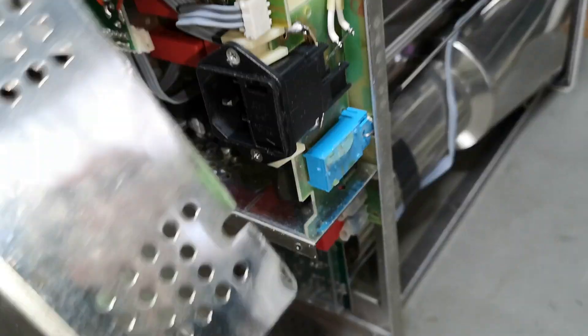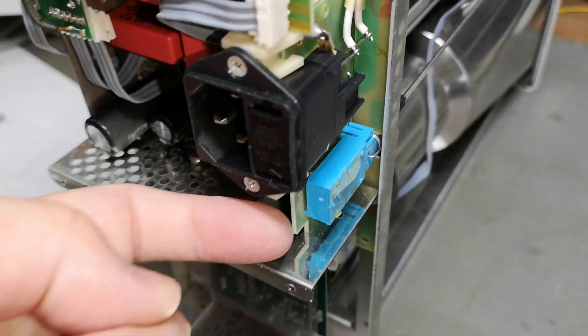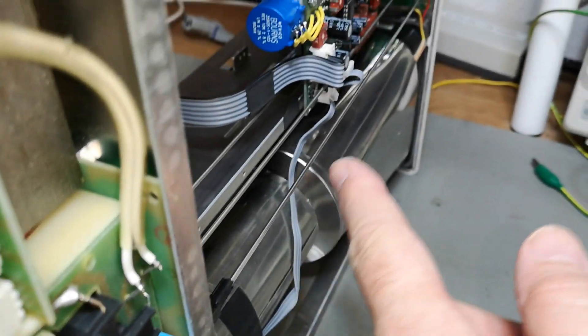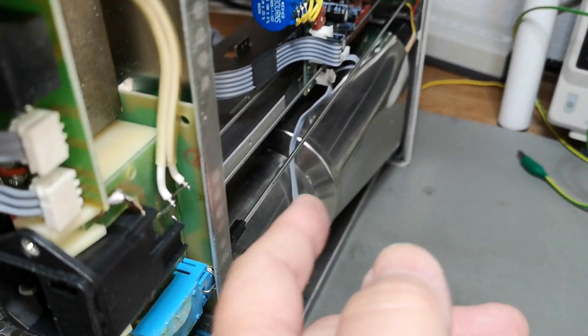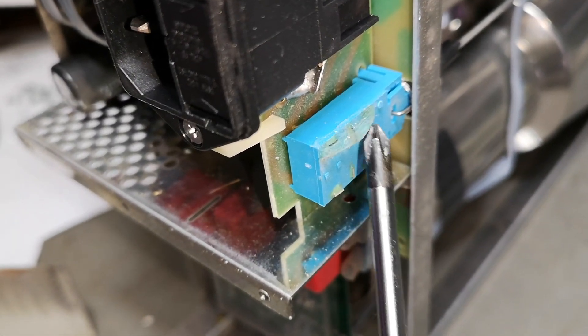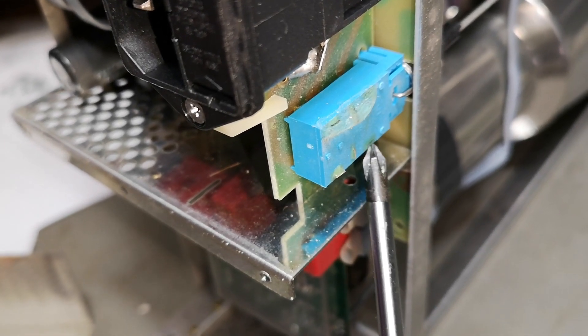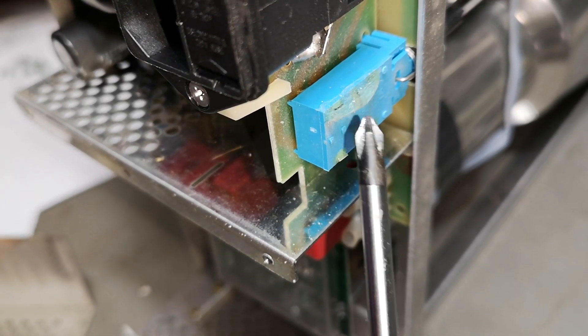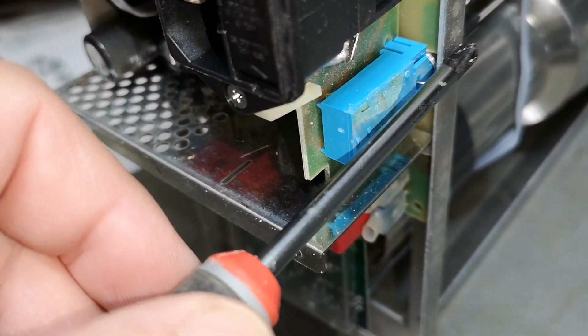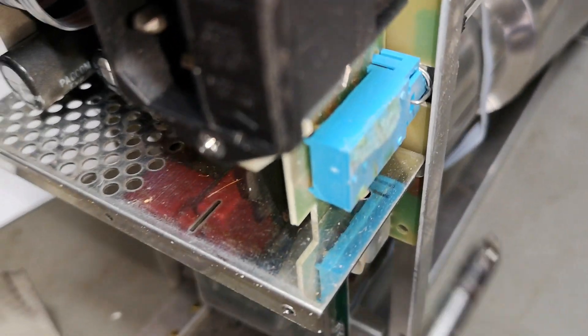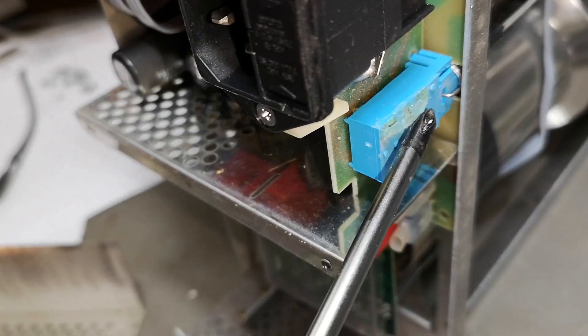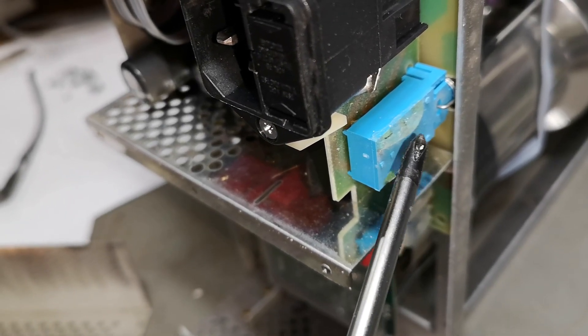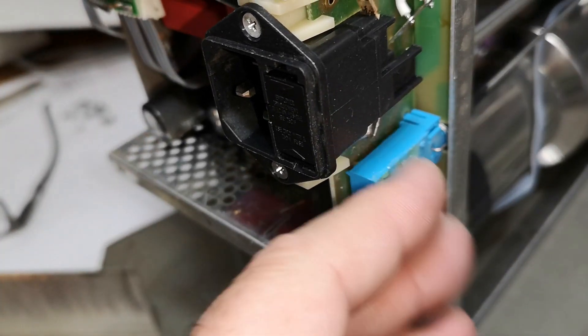There is a hole here in this plate that is made for this little metal thing, and it is supposed to be all this way down. Otherwise this push right here for the on-off switch is going to be bent and then it doesn't really work that well. Look what they've done - they have added silicone isolation on the pins and they have cut the pins. I bet it's only half of the switch that is used, the upper pins here, and that is to create a safe distance. They probably failed isolation tests and then they tried to fix it this way. This silicone glue here is a very effective isolator and now they're passing the high voltage security tests.